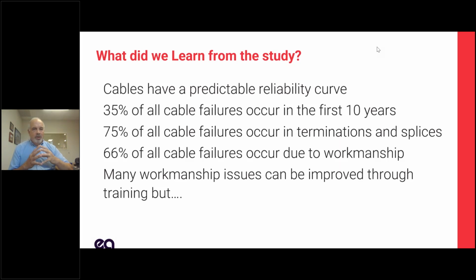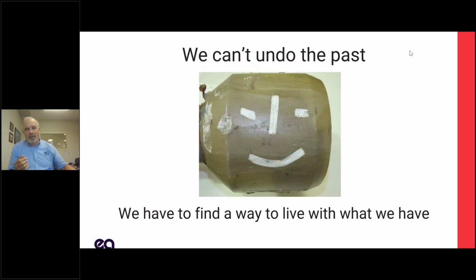So from this study, what did we learn? Cables do have a predictive reliability. 35% of all cables will fail in the first 10 years. Sorry, said that wrong: cable failures occur in the first 10 years. And it's in the terminations and it's workmanship. So we can fix a lot of the workmanship and we can do more training, but as someone once said, we can't fix stupid. This is actually from a cable termination where the joiner did not know what to do with the white mastic, so he made a smiley face. This cable failed pretty quickly. We've got to look at workmanship.